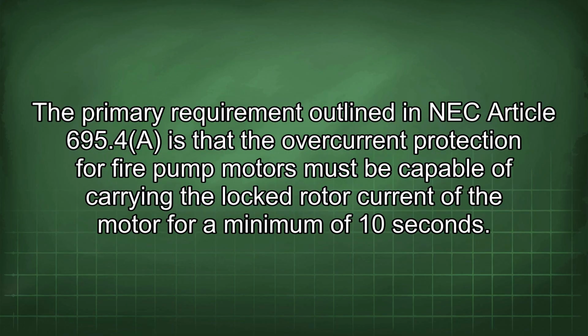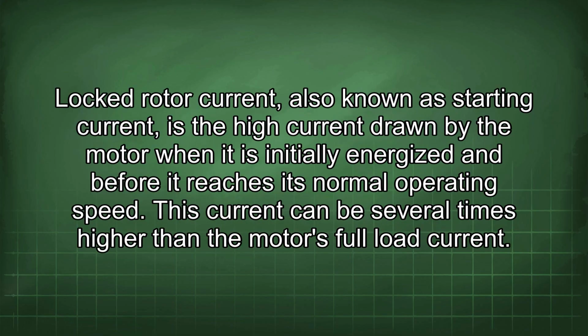The primary requirement outlined in NEC Article 695.4 is that the overcurrent protection for fire pump motors must be capable of carrying the locked rotor current of the motor for a minimum of 10 seconds. Locked rotor current, also known as starting current, is the high current drawn by the motor when it is initially energized and before it reaches its normal operating speed. This current can be several times higher than the motor's full load current.